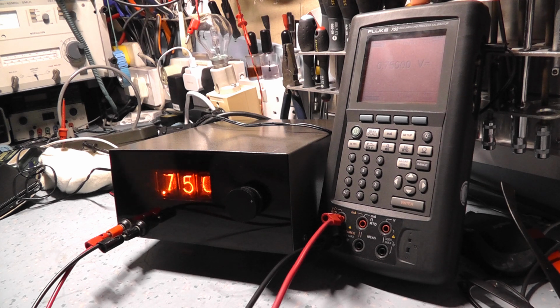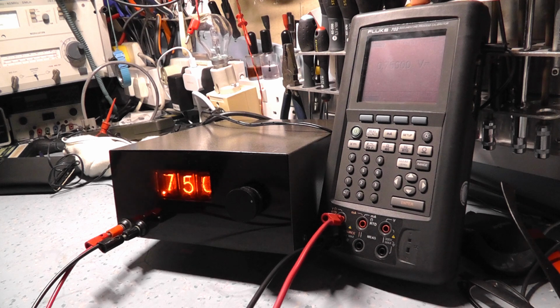Presently we're sourcing from the Fluke source calibrator. We're actually sourcing a 750 millivolt signal. You can see it's spot on and rock steady. It's calibrated up nicely with that adjustment of that reference voltage. The actual silk screen on the meter says adjust to 12 volts, which I did initially when I first got the meter, but then I couldn't get anything in calibration, certainly in the lower ranges. I was on the end of the pot travel and I couldn't get it to the reading I needed. If I altered the reference voltage, then I could. So basically that's what I've done. I've shifted the reference voltage. As long as the reference voltage stays stable, I can't see it being a problem.